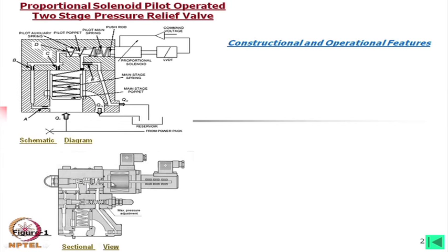Now, this spool is being driven by the proportional solenoid, and this drive force is being transmitted through a spring, not directly. This poppet is not directly connected to the solenoid spool, it is connected through a spring. Now, this is the input for the current or voltage, whatever it might be, to the proportional solenoid.